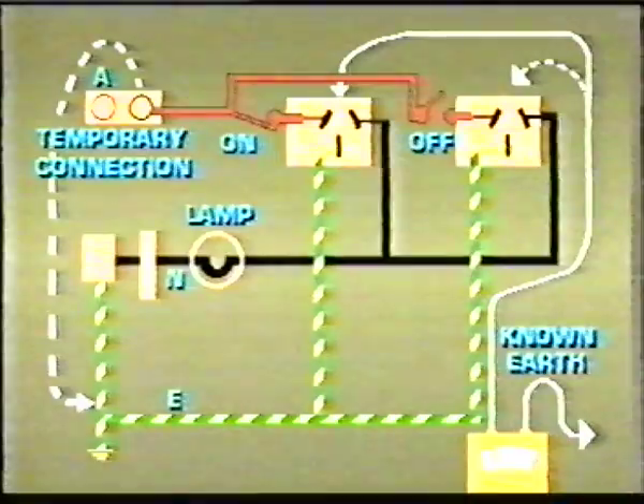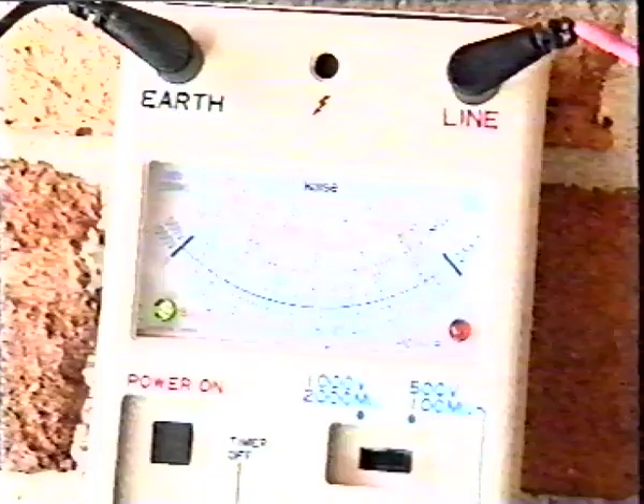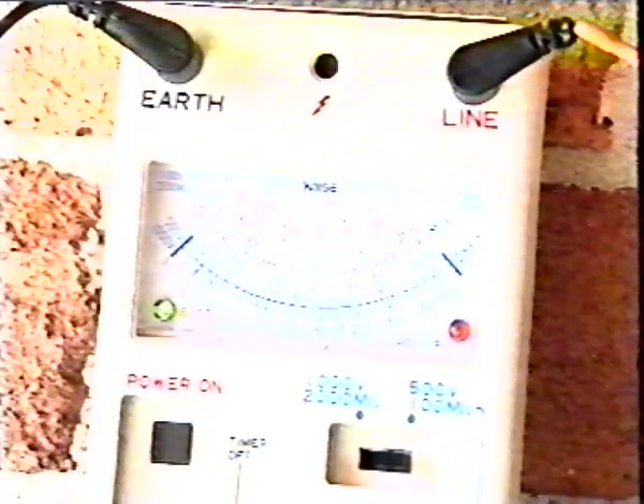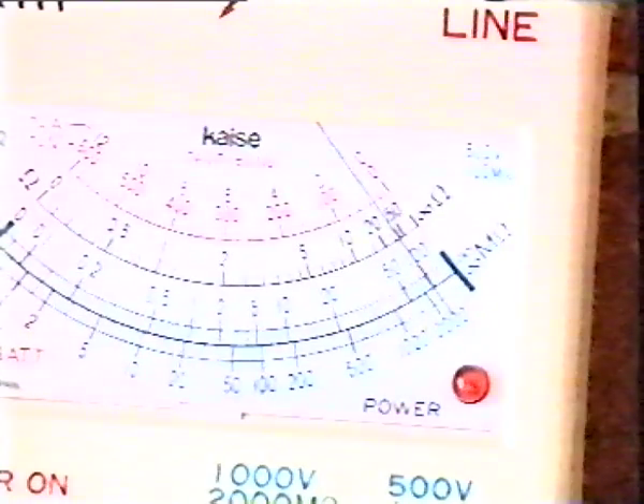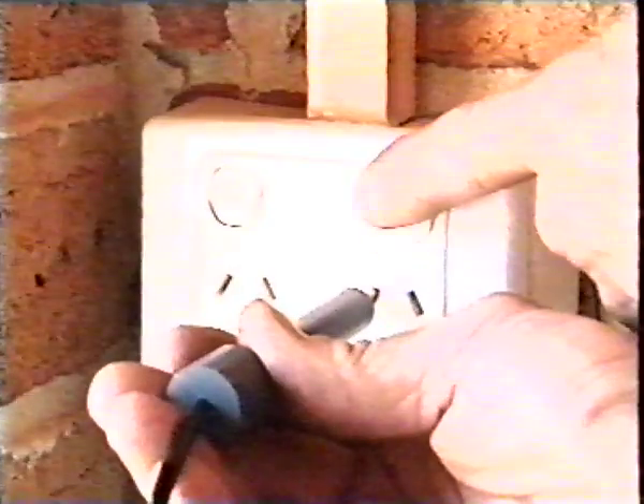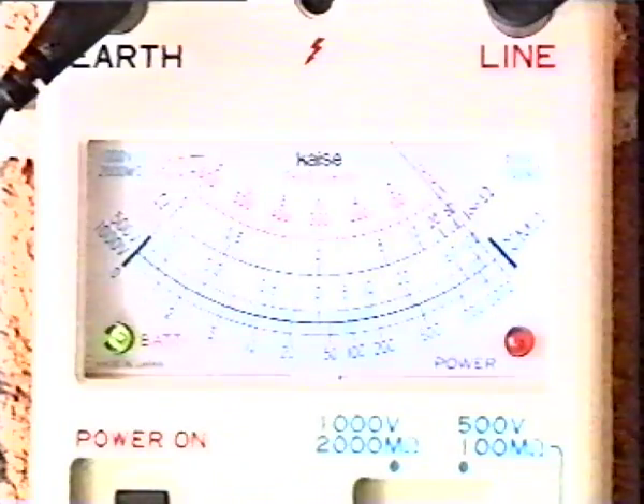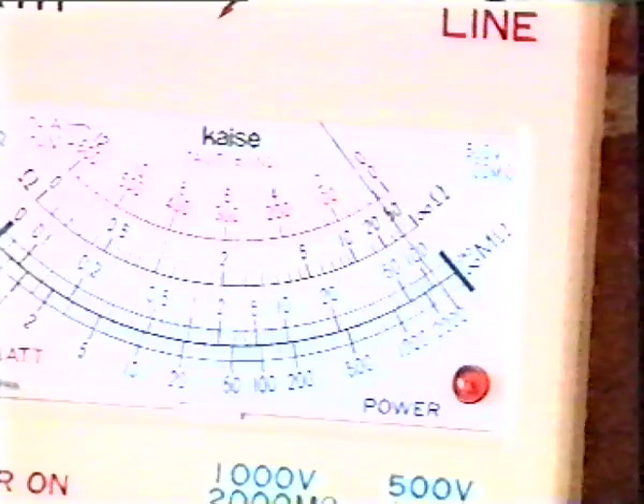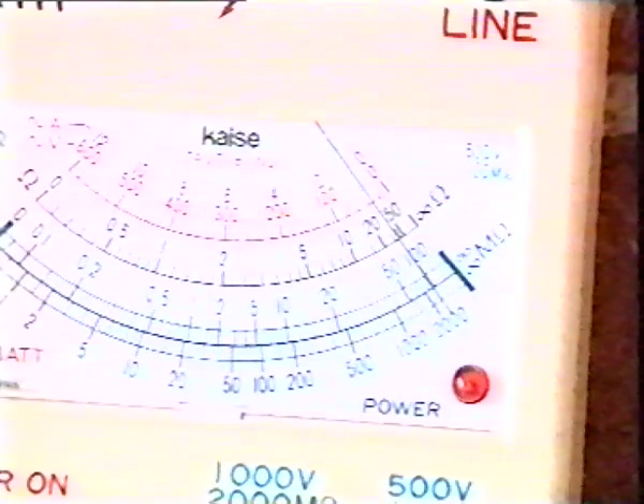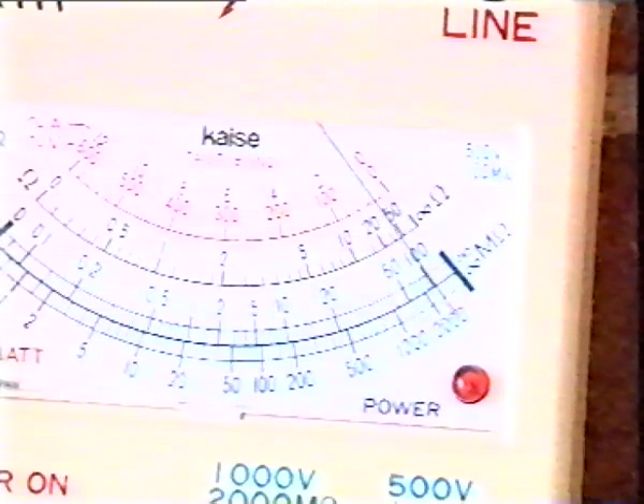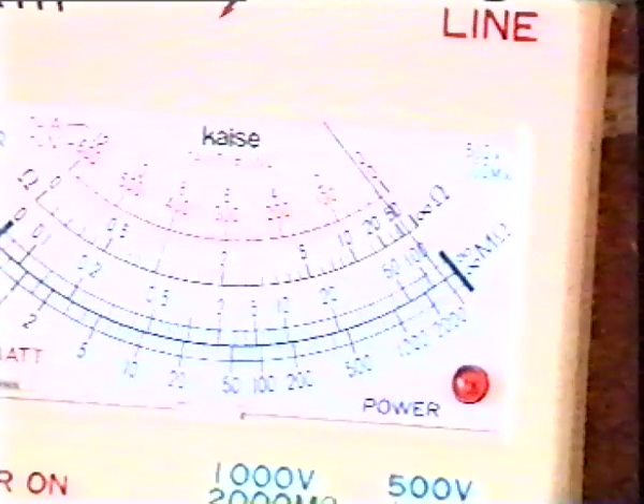Correct polarity is proved when, with the switch on, the active to earth indicates a short circuit and neutral to earth indicates lamp resistance. And with the switch off, active to earth indicates an open circuit, while neutral to earth indicates lamp resistance. A 60-watt lamp has a cold resistance of approximately 70 ohms.